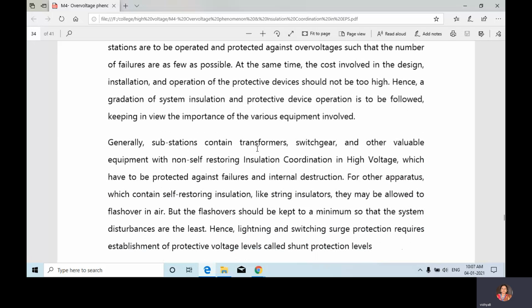Next, substations contain transformers, switchgear, and other valuable equipment with non-self-restoring insulation, which have to be protected against failures and internal destructions. You already know about a substation, because you already went for an internship. You know how a substation is arranged, what equipment and protective devices they use, and how they maintain them. If any fault occurs, how do the relays and protective devices react, and how do internal disturbances or destructions happen?